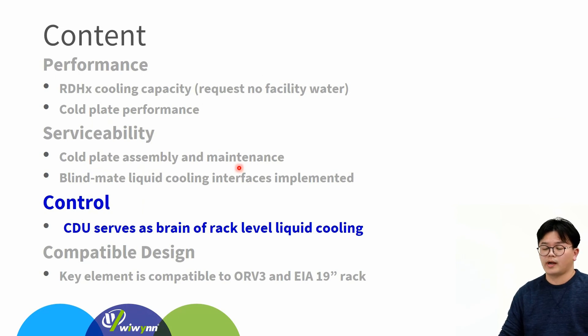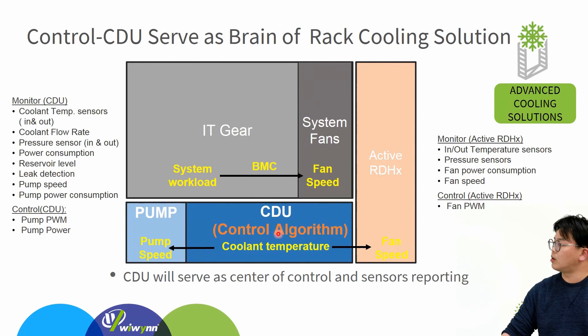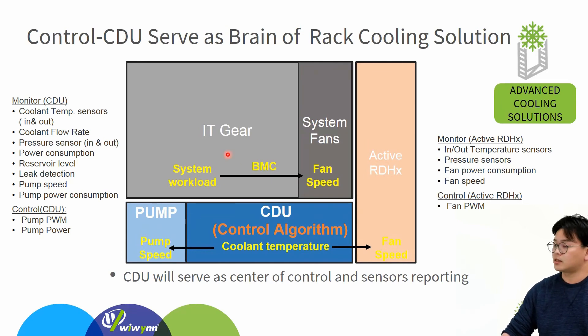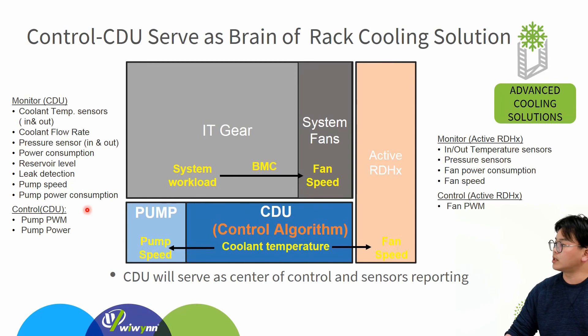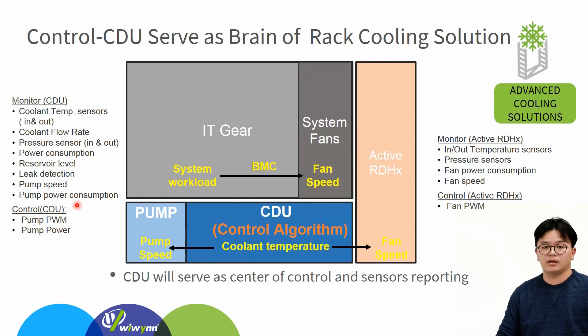As mentioned, the solution will have an independent cooling control system. The CDU will own control over the fans on the active rear-door heat exchanger and the pump speed in the CDU. For IT gear, the CDU will control the system fans via BMC. The CDU can also monitor all sensors and the status of both the CDU and the rear-door heat exchanger. Regarding cooling power estimation, we will design the CDU to monitor its temperature as well as power consumption, for future use in estimating cooling power consumption.